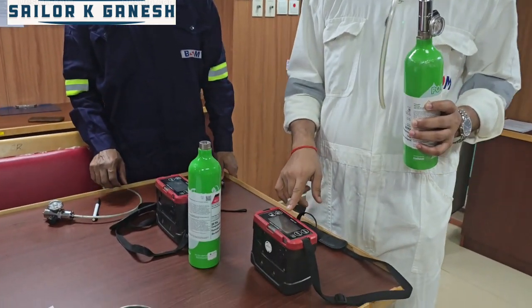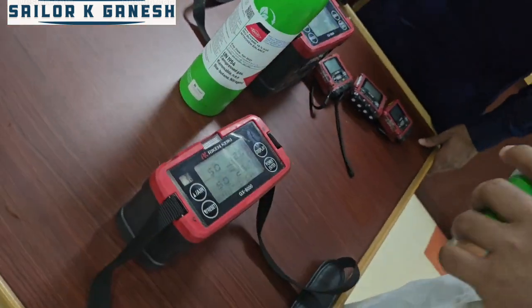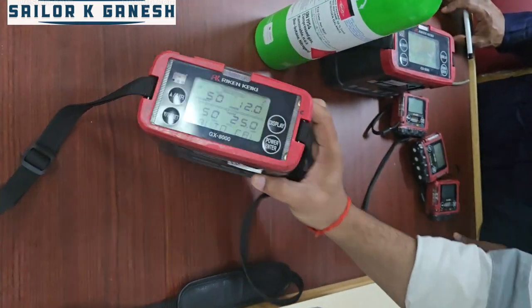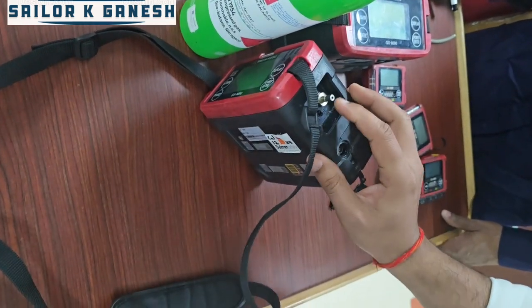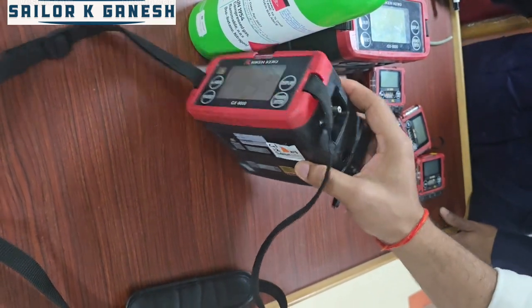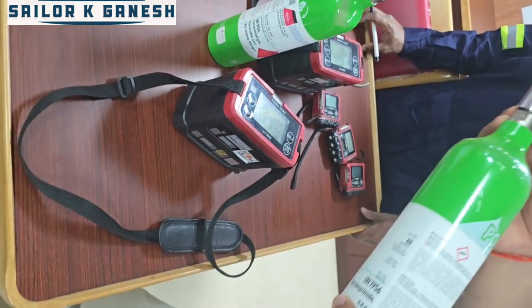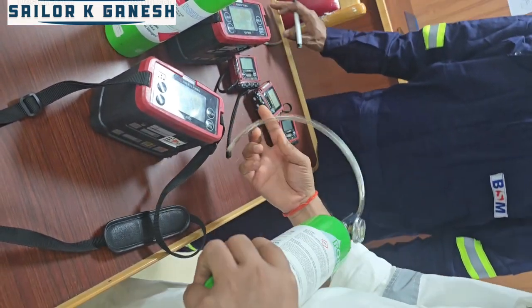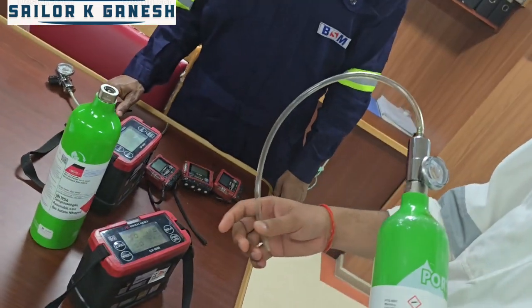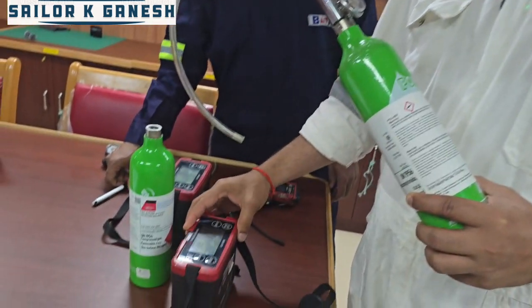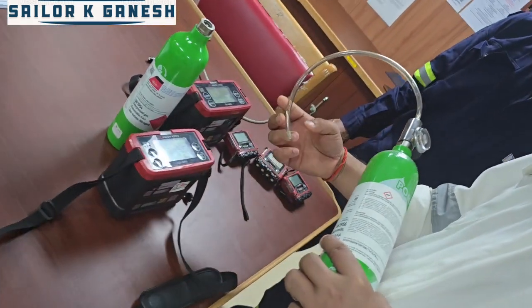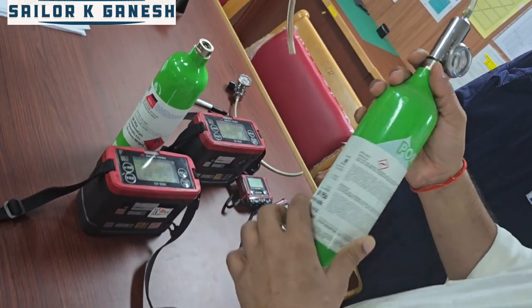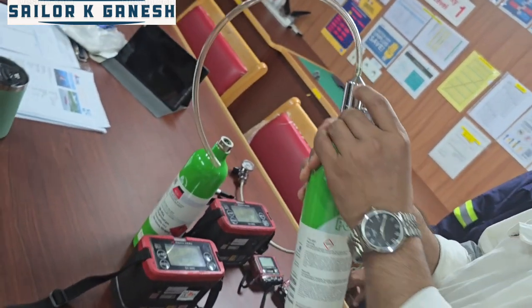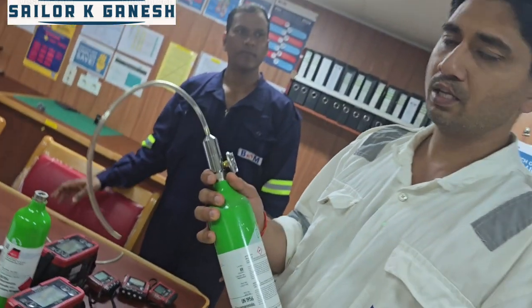After going to this auto cal mode, you must connect this line to the inlet side of the gas meter. This is the inlet side and this is the outlet side. Before opening this flow meter gauge, if you connect this to the inlet side, you will get the flow failure alarm. So once you open this, only then do you connect this to the inlet side. And we have a flow meter over here, so you don't require the bag to fill the gas.